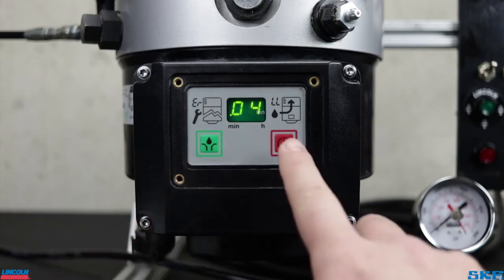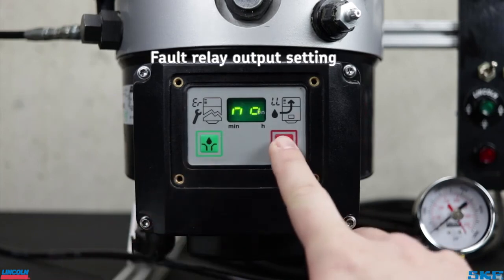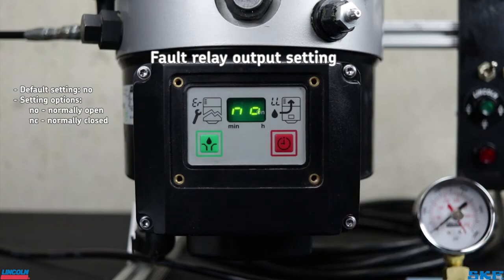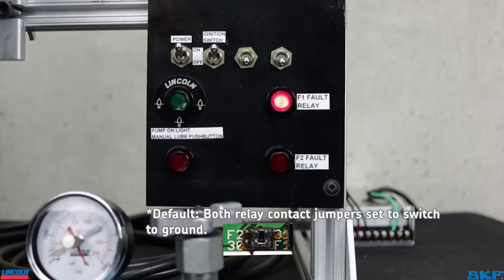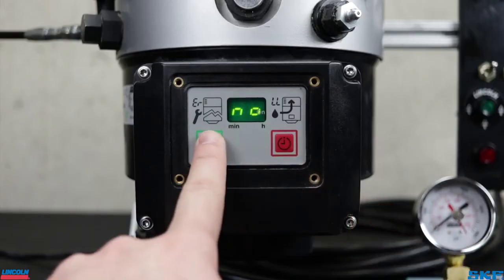The next setting will be P4. This setting is factory set to NO or normally open. It is for the alarm contacts when remote monitoring is necessary, such as having a dash or panel mounted light to signal a fault or sending the signal to a PLC. Should a fault show on the screen in this setting, the alarm contact will close and your light will illuminate on the remote location, signaling a fault. The opposite will occur if setting to NC or normally closed. Lights will stay on but shut off should a fault occur.